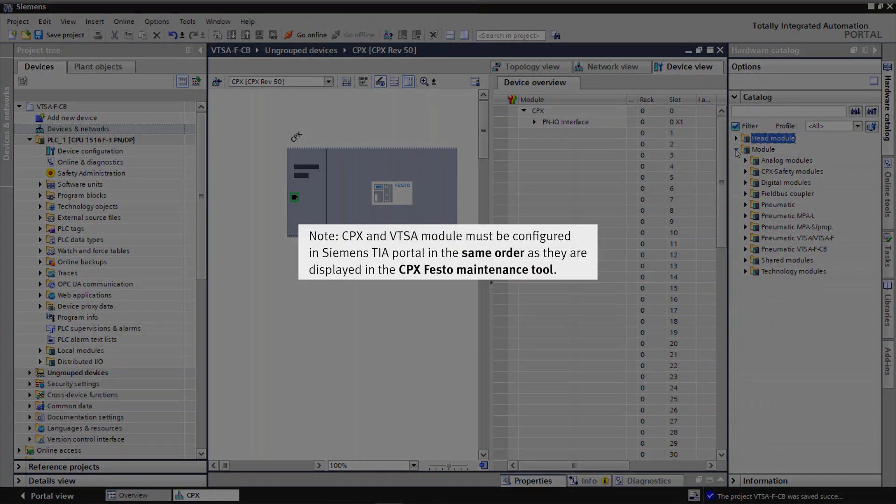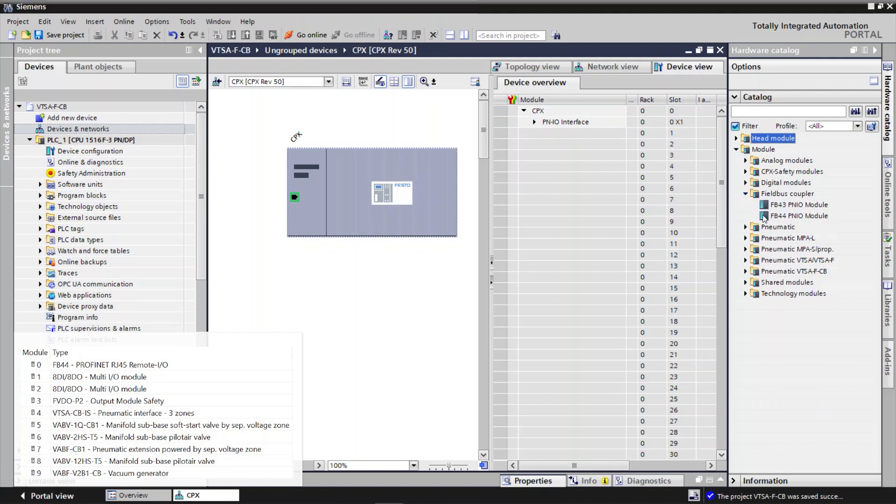Note, CPX and VTSA module must be configured in Siemens TIA portal in the same order as they are displayed in the CPX Festo Maintenance Tool. Drag and drop the modules needed as per the application.